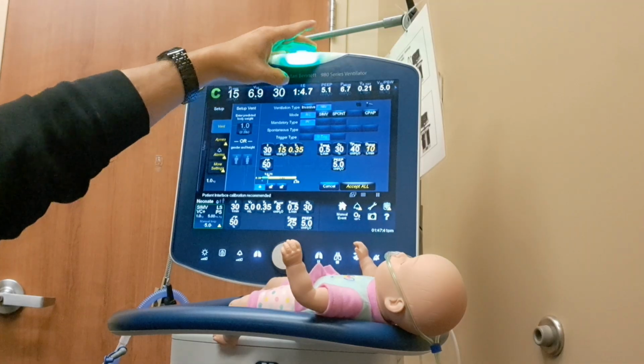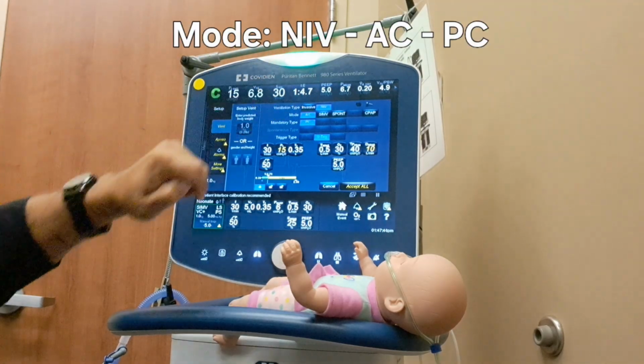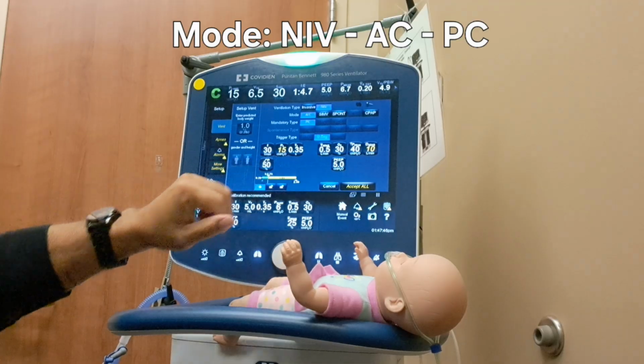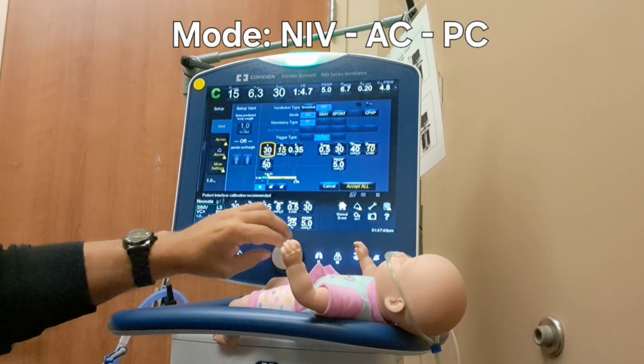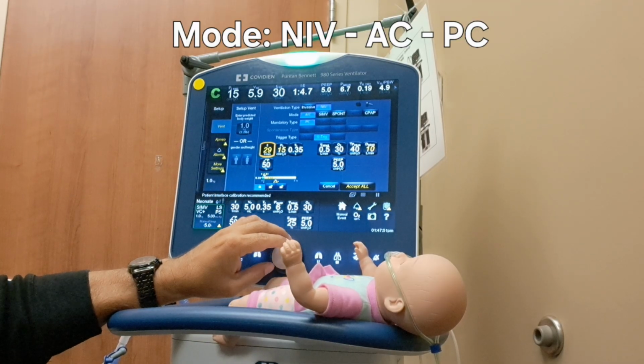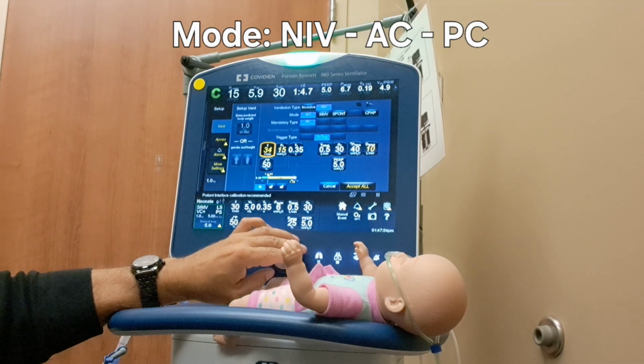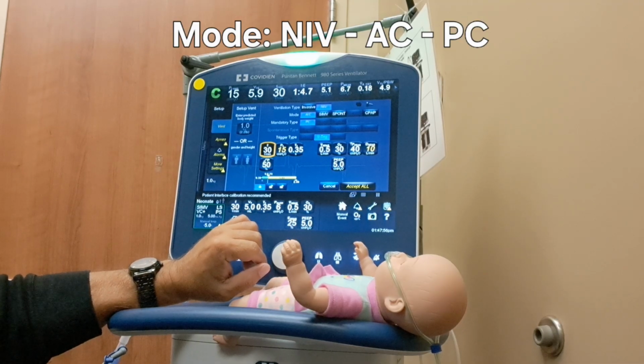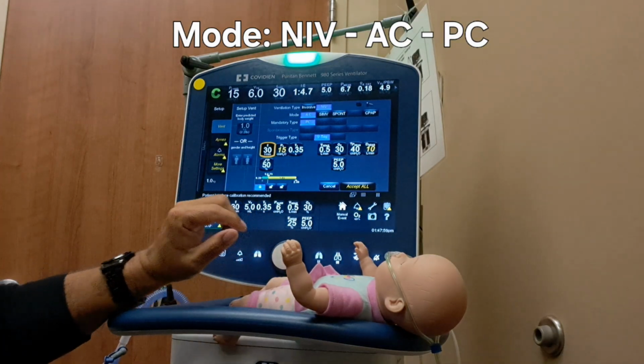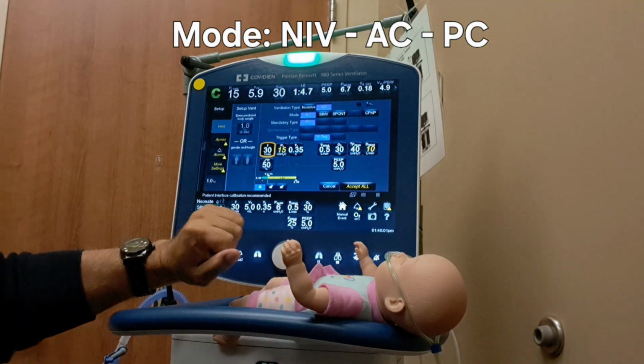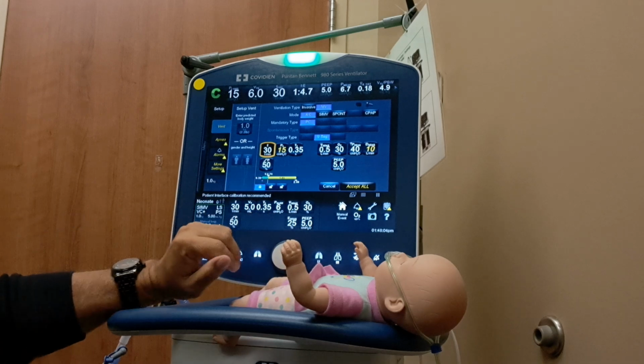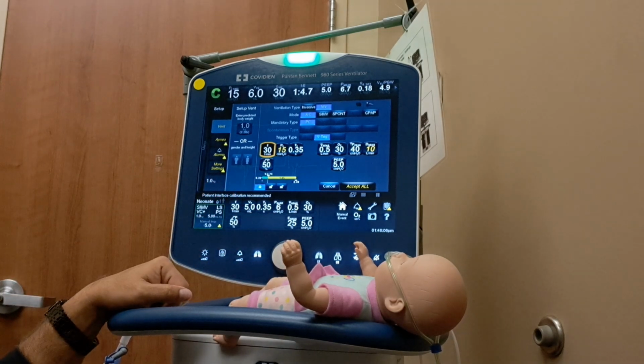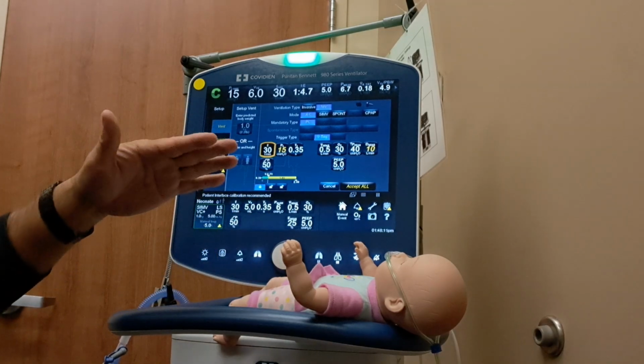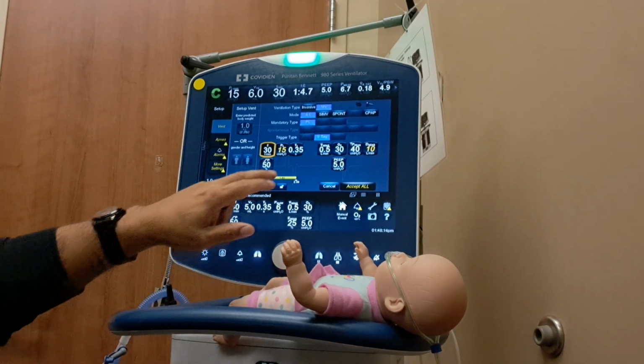We'll select NIV at the top and then assist control. So it'll be NIV, assist control, pressure control. And then we'll put in our settings. A rate of 30 is usually pretty good to start with. You go up or down, but 30 is usually a pretty good place to start. Our total PAP is set by adding your PEEP to your pressure that's set. So my PEEP's at 5, my pressure set's at 15. So we'll start off with a pressure of 20, which is okay, reasonable. And you may go higher, maybe a little bit lower, but 20 is pretty reasonable.